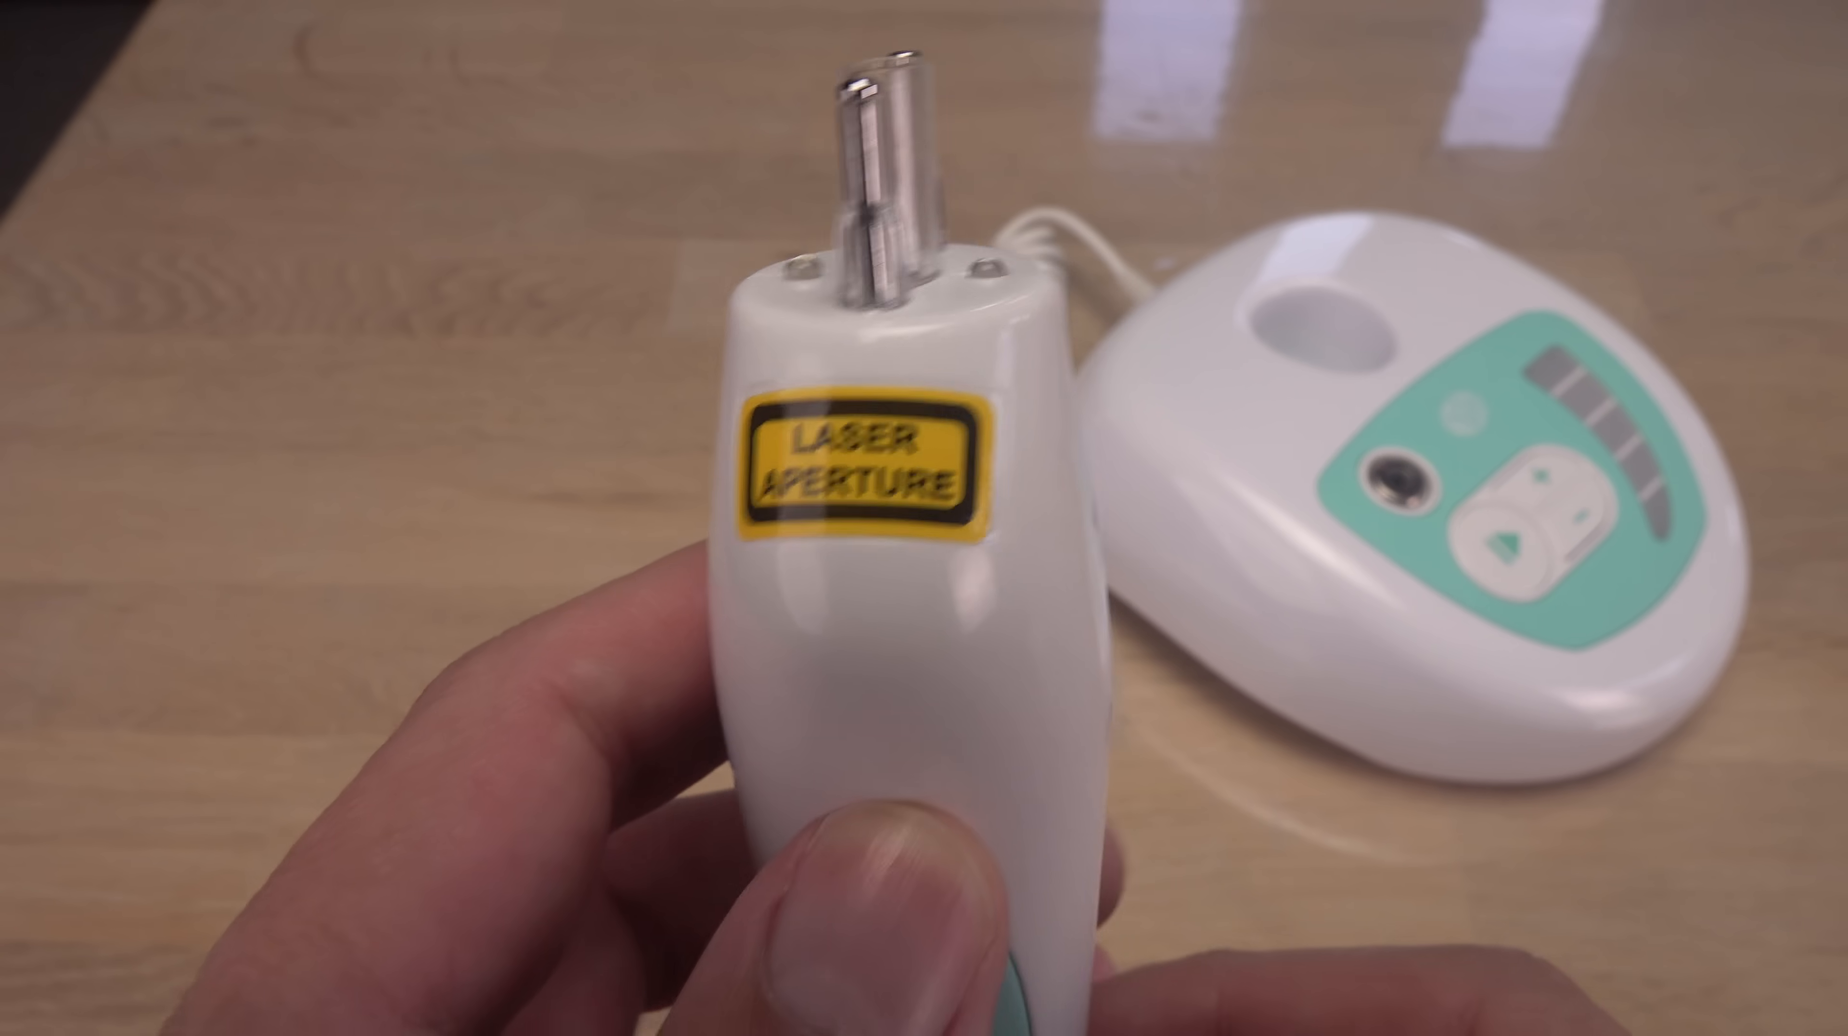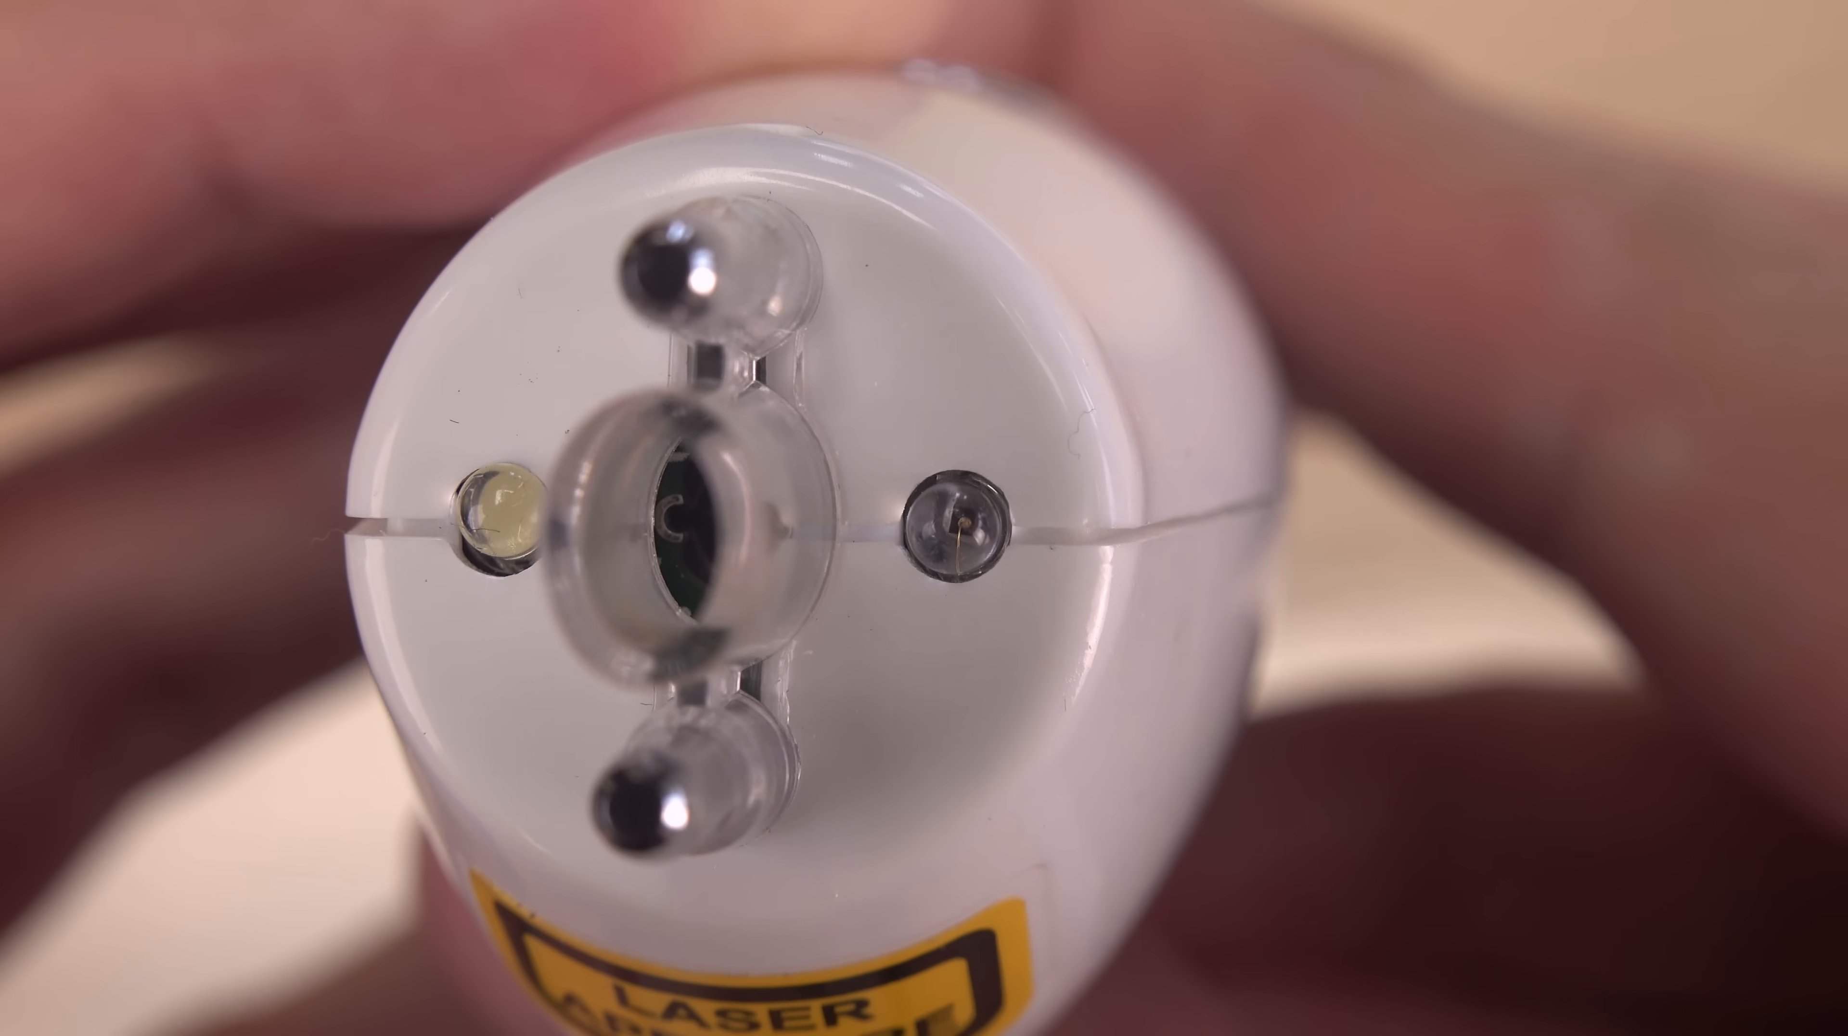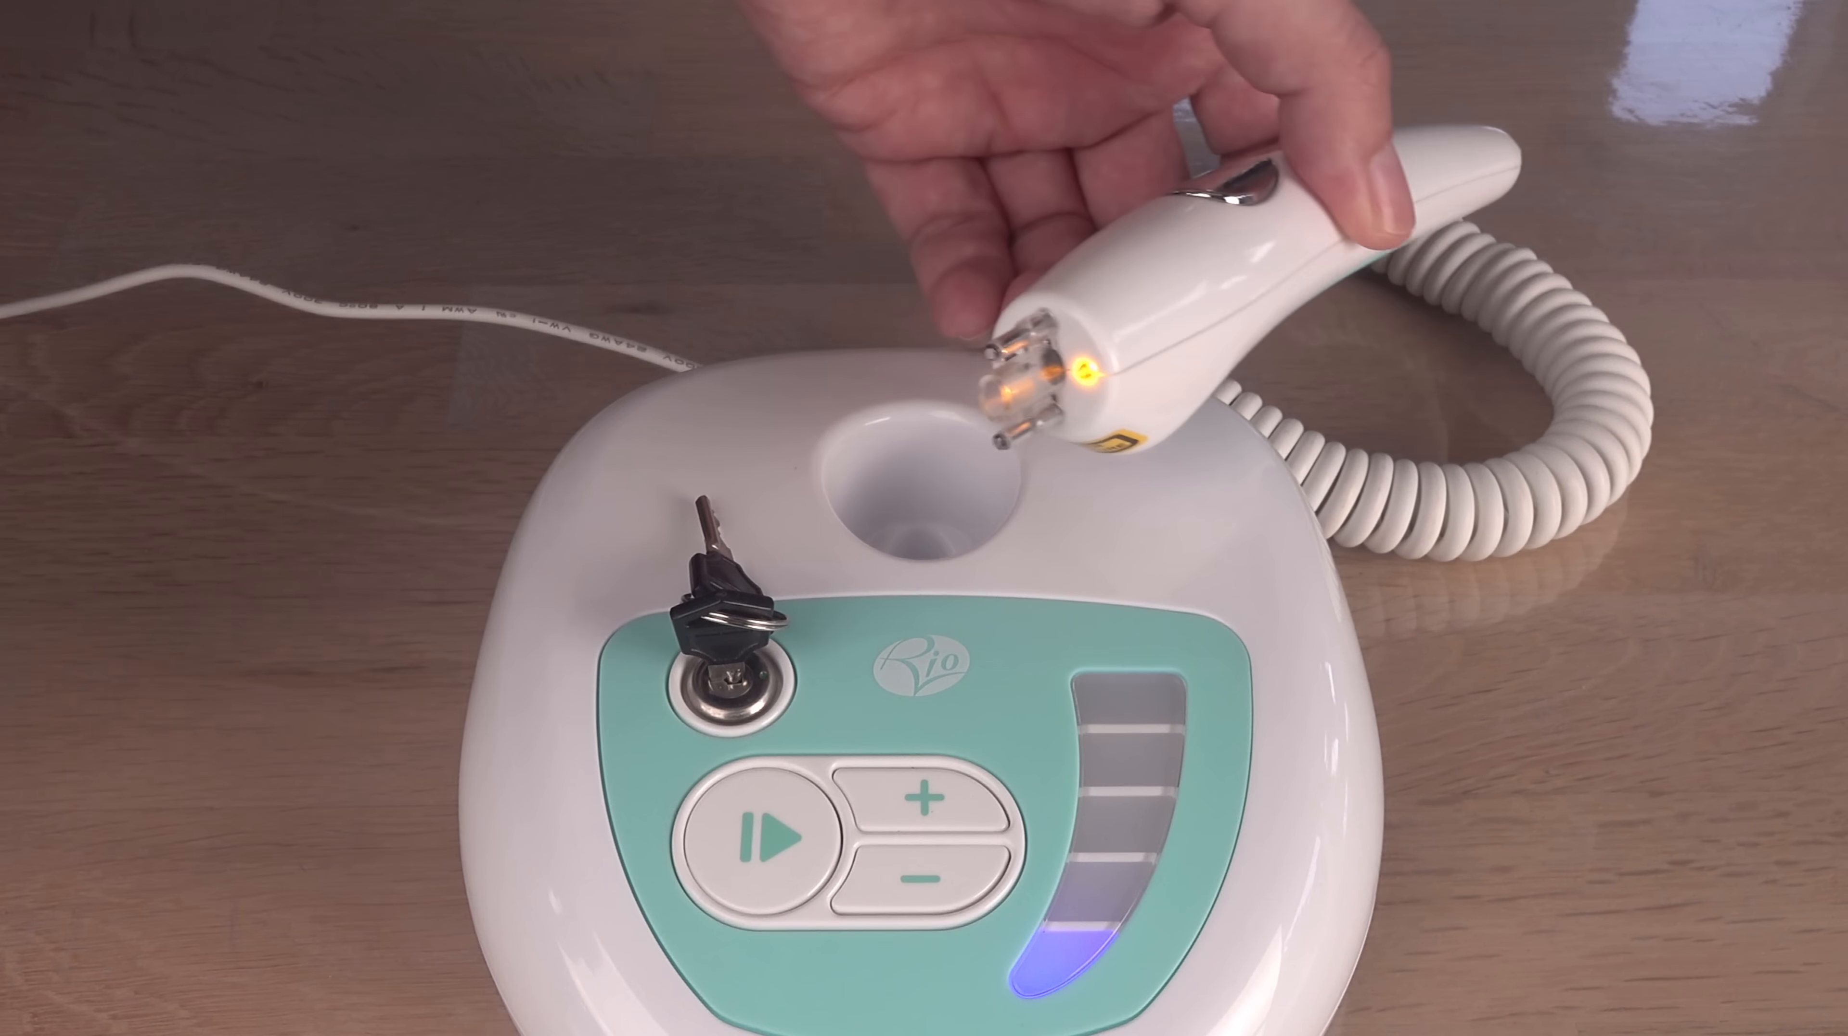But before we test how strong it is, I want to measure the color spectrum of the four diodes built into the laser head. Yes, four. There are two different laser diodes inside. When the handpiece is unlocked, using a key and security combination, an LED emitting visible light turns on.